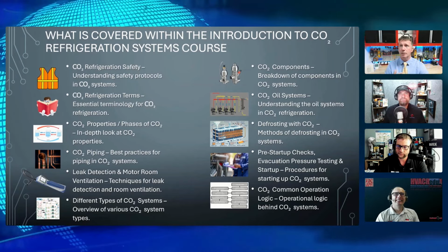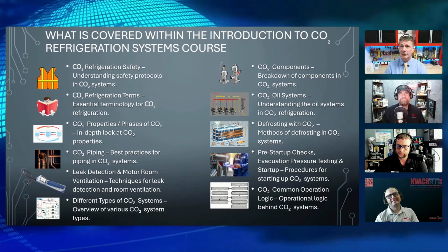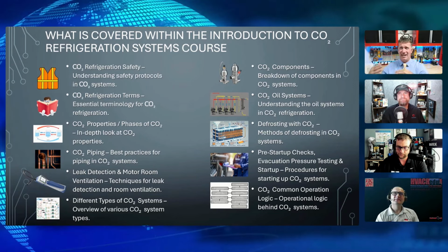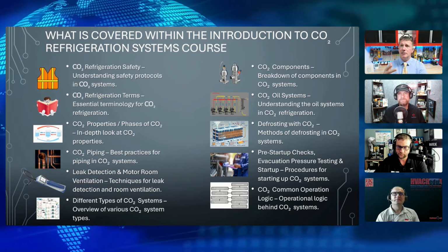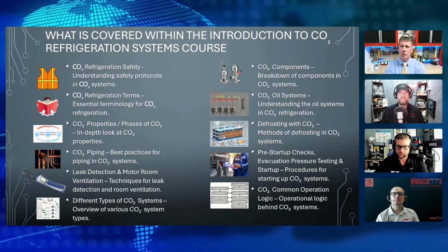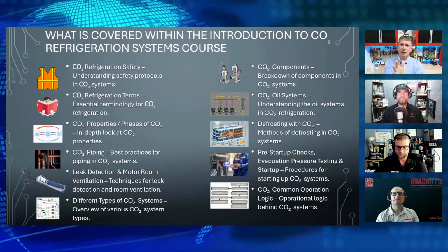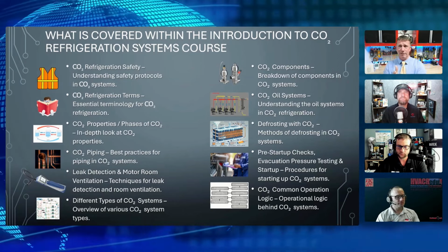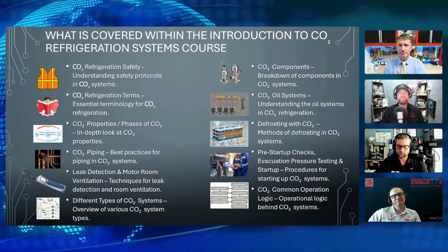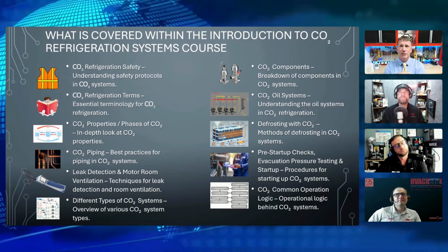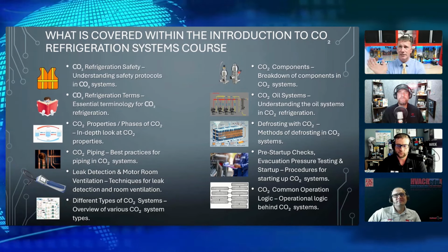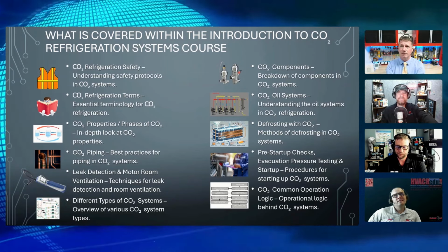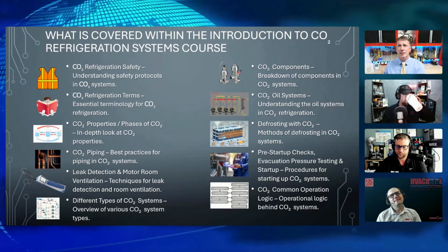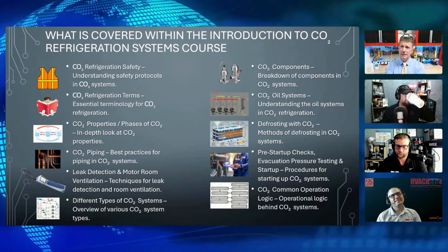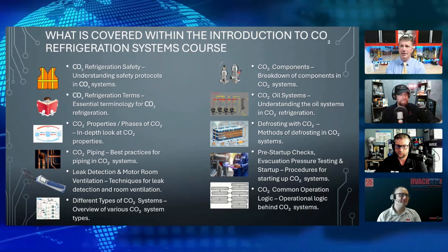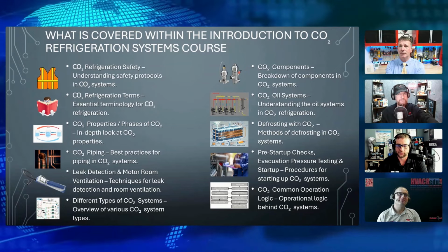See, I was the nerd that walked into my rack room and pulled up my E2 just to see if any of my sensors had any kind of trending whatsoever. So if we're looking at our graphs and we're looking at CO2 detection, when we say we're going to be doing a retrofit of a grocery refrigeration system, and I remove my traditional HFC or HCFC refrigerant-based refrigeration rack and I'm going with a CO2 system, am I going to implement a CO2 monitoring system into that, a refrigerant leak detection? 100%. Okay. 100%.